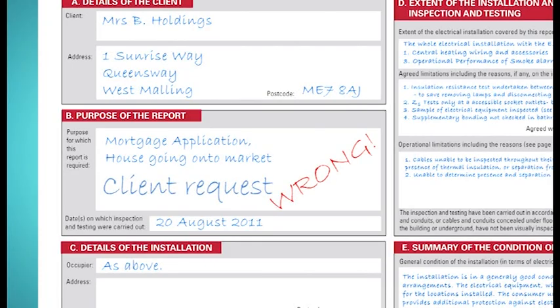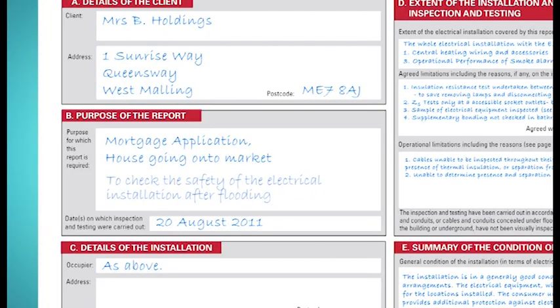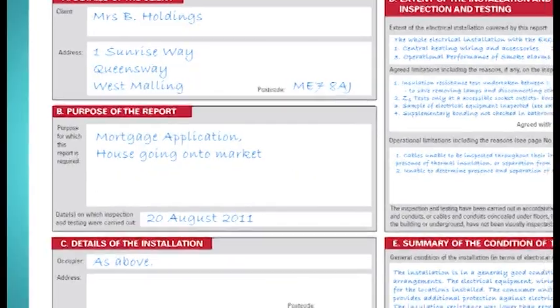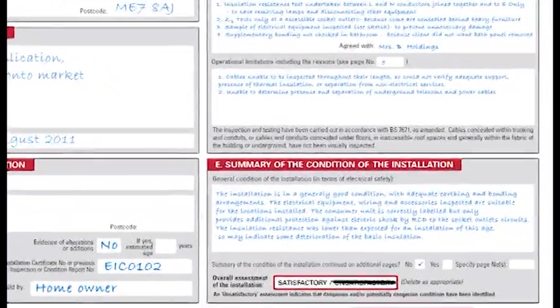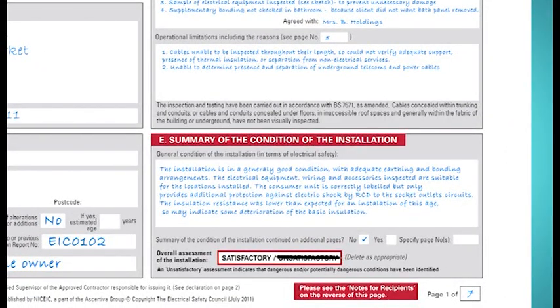It would not be right to put something like client request or to check safety here, although if you put to check the safety of the electrical installation after flooding, this would be acceptable. For the summary of the condition of the installation, I've written this. The installation is in a generally good condition, with adequate earthing and bonding arrangements. The electrical equipment, wiring and accessories inspected are suitable for the locations installed. The consumer unit is correctly labelled, but only provides additional protection against electric shock by RCD to the socket outlet circuits. The insulation resistance was lower than expected, so may indicate some deterioration of the basic insulation.